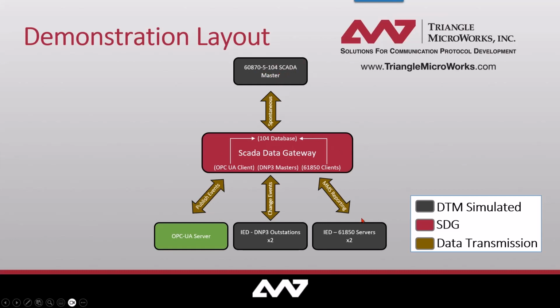This dark gray color will be simulated in DTM, and we'll also have an OPC UA server that we'll be interacting with. So the idea is all of the data will need to come from these RTUs and this OPC UA server, and eventually be put into our gateway through 61850 clients, DNP3 masters, and an OPC UA client. All of that information, through mapping, equations, and similar methods, will be concentrated into a single database and then published up to our SCADA Master.